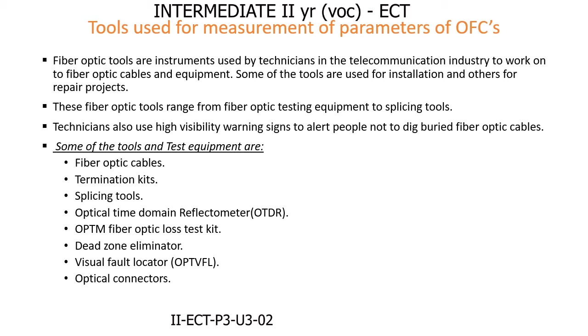Optical time domain reflectometer OTDR. OTDR applications in servicing. An optical time domain reflectometer OTDR is an optoelectronic instrument used to characterize an optical fiber. An OTDR is the optical equivalent of an electronic time domain reflectometer. It injects a series of optical pulses into the fiber under test and extracts from the same end of the fiber light that is scattered or reflected back from points along the fiber. The strength of return pulses is measured and integrated as a function of time and is plotted as a function of fiber length.